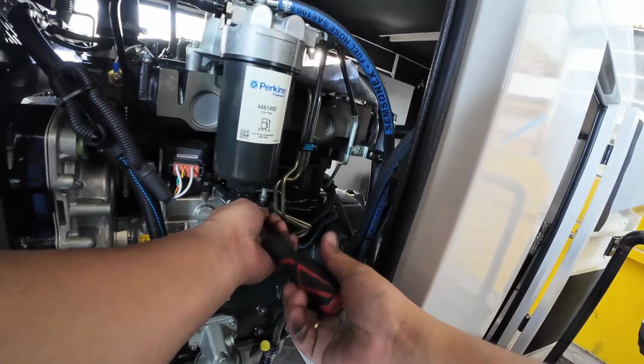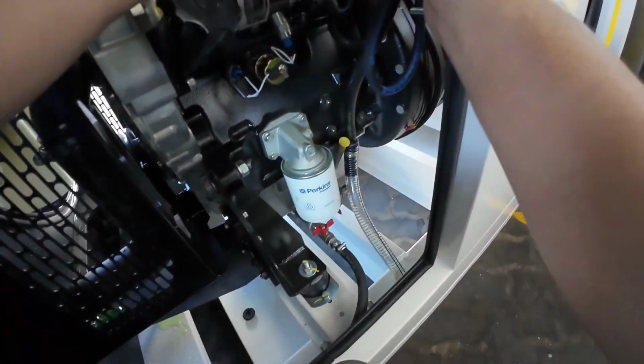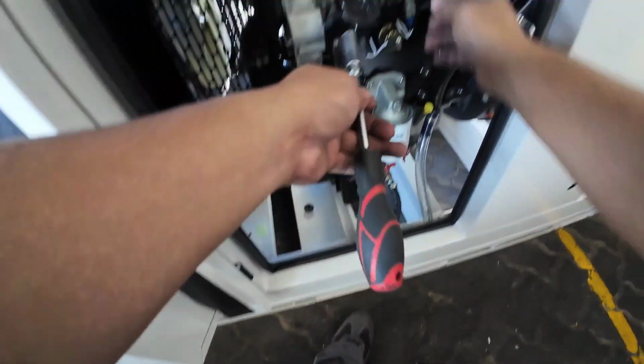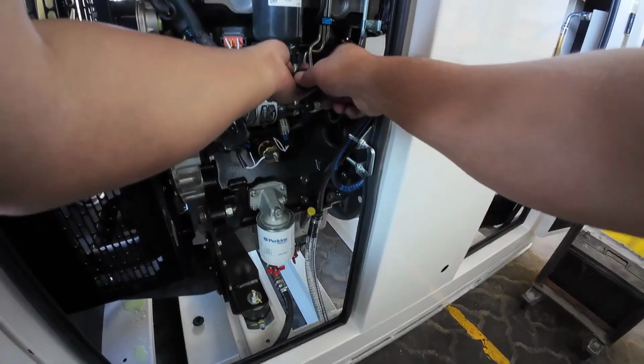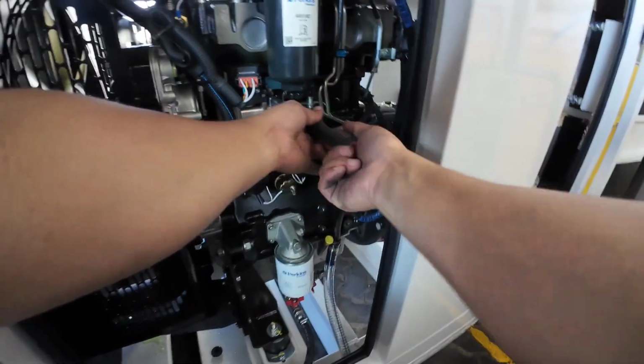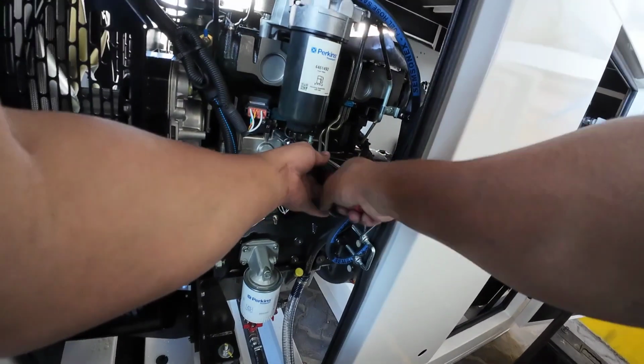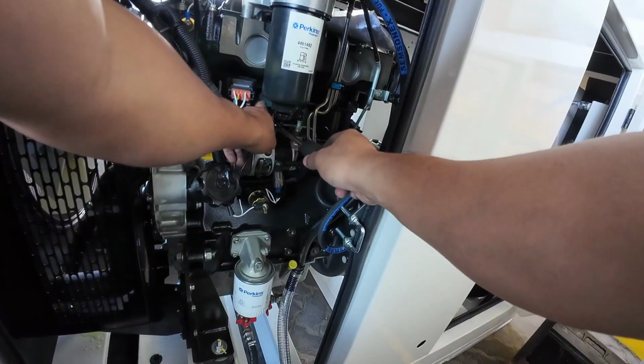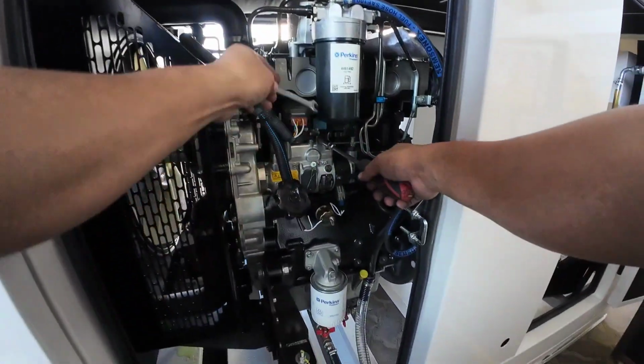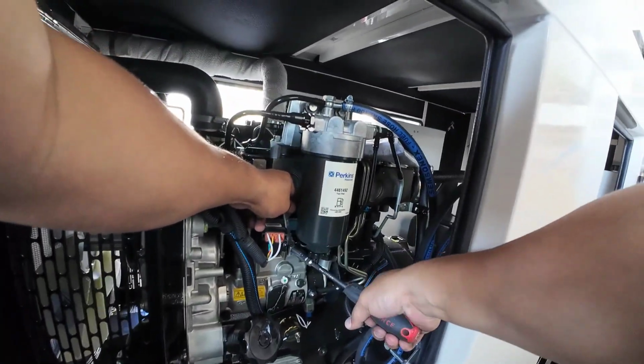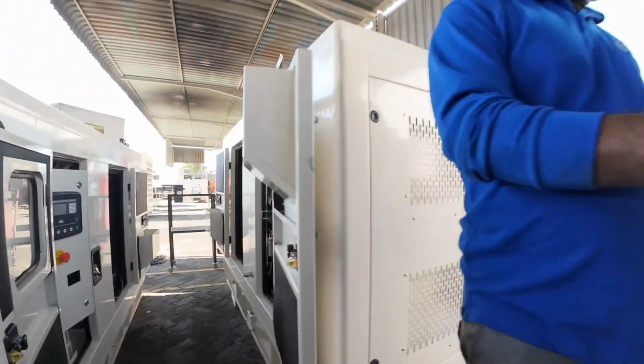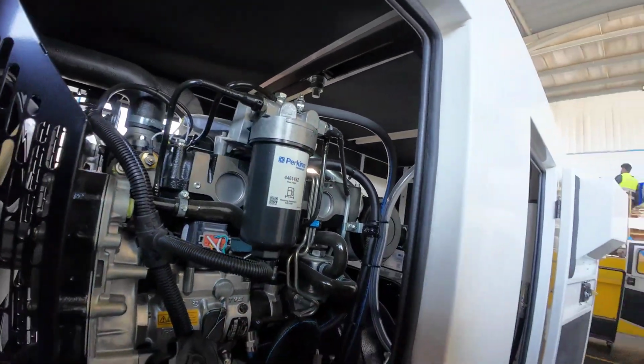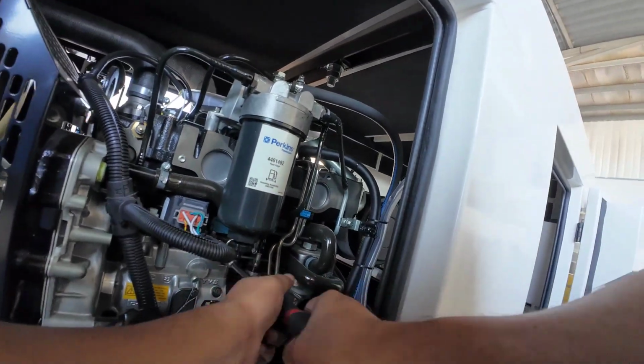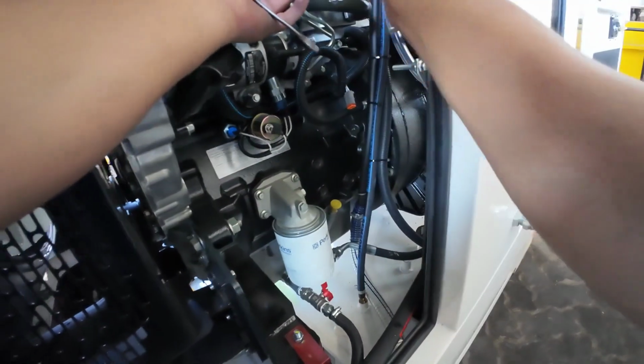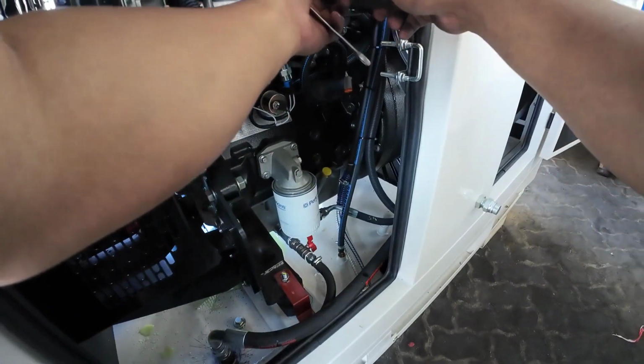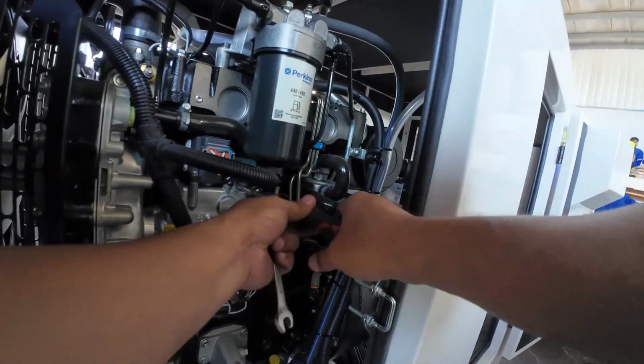At this point I'm done with the configurations for all of the modules and our actuator. Now I need to adjust the lever for our actuator, so it can have the windows for automatic adjustment of the fuel, depending on the load we apply. It can move automatically, so it's not difficult for our actuator to react to that speed, because this one is 60 hertz. We need to do that for all these generators, adjusting one by one the lever for our injector speed, so it will work properly.